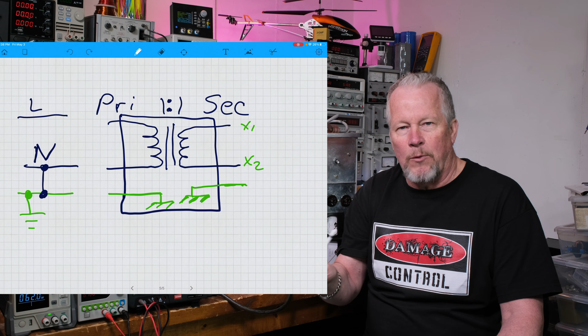So this transformer, the way I'm showing right now, shows that the secondary winding is just floating. It's not referenced to anything, right? So if you went, well, you know what, I want to recreate what I had at the other side. Whatever device I plug into this thing, I want it to have a place where it pops a breaker if something touches this, because if something touches it, I want to know it. I want it to pop a breaker. I don't want this thing to be connected to that winding voltage.